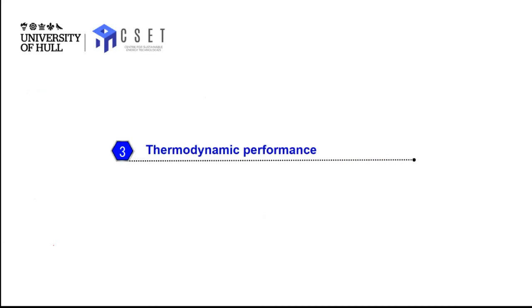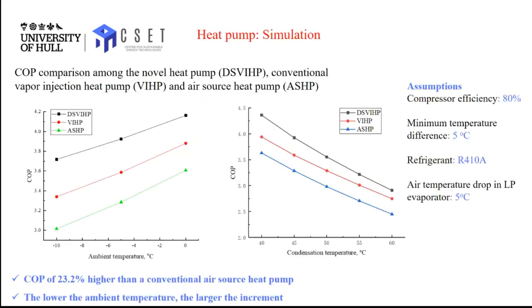So talking about thermodynamic performance, we tested our new heat pump, comparing its performance with a traditional vapor injection heat pump and an air source heat pump. This diagram shows the correlation between COP and ambient temperature, and COP and condensation temperature. You can see, compared to the traditional air source heat pump, our heat pump can achieve around 23.2% higher COP, and at low ambient temperature the COP increase rate will be higher.